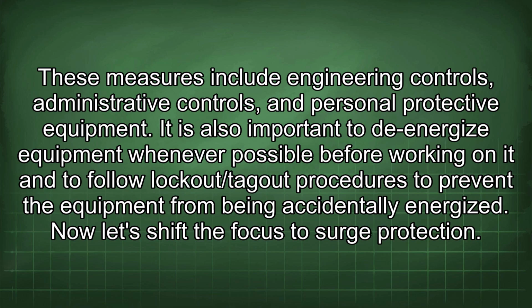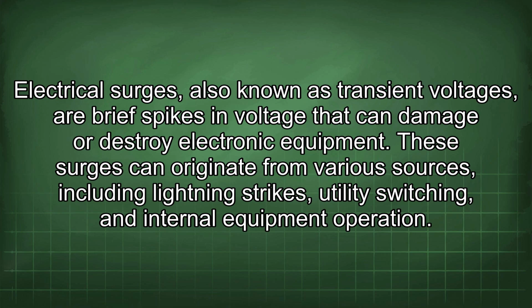Now let's shift the focus to surge protection. Electrical surges, also known as transient voltages, are brief spikes in voltage that can damage or destroy electronic equipment. These surges can originate from various sources, including lightning strikes, utility switching, and internal equipment operation.